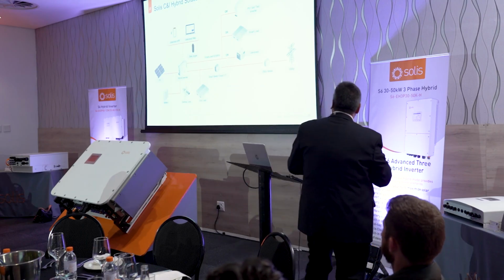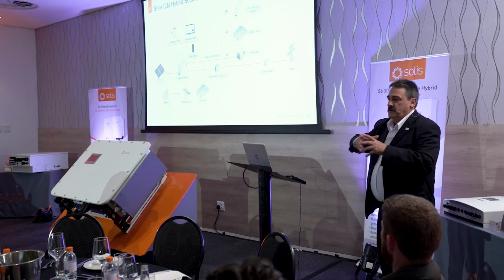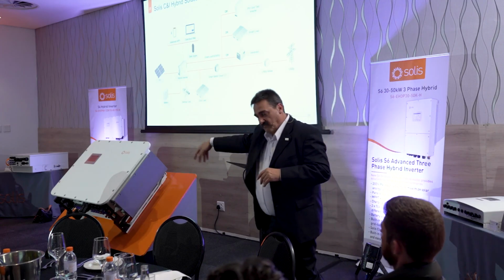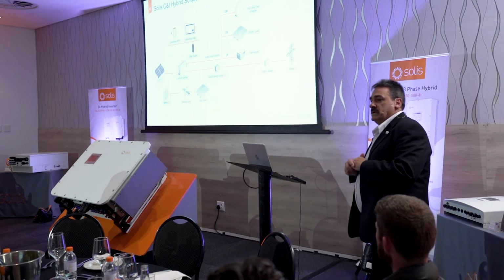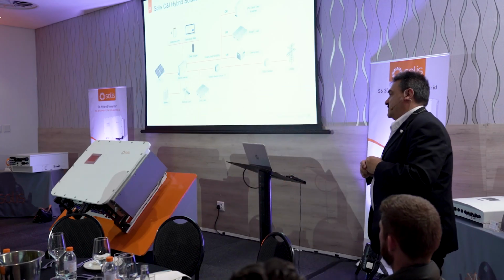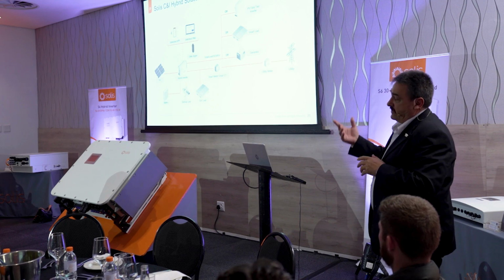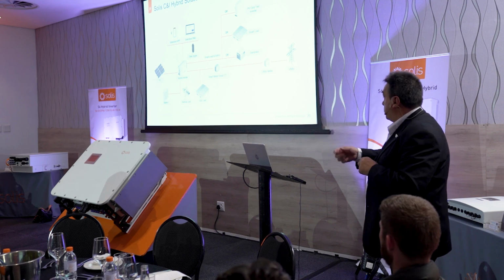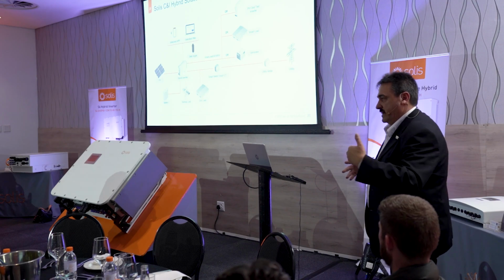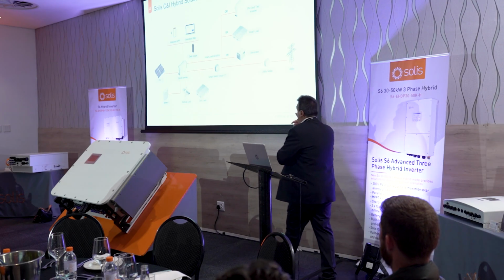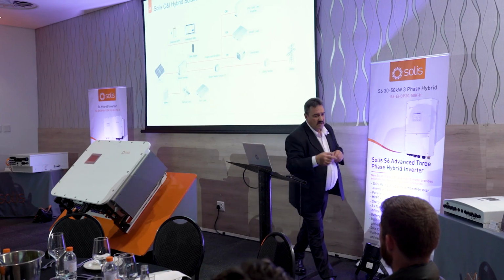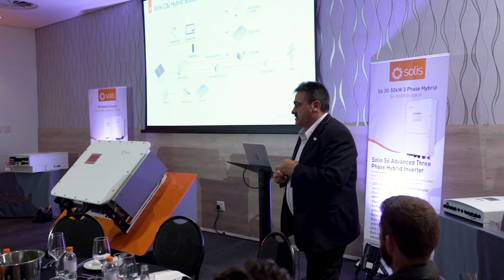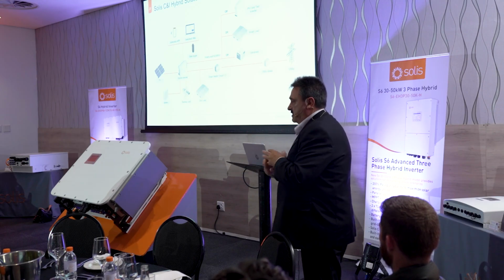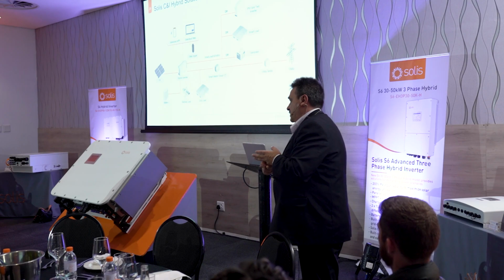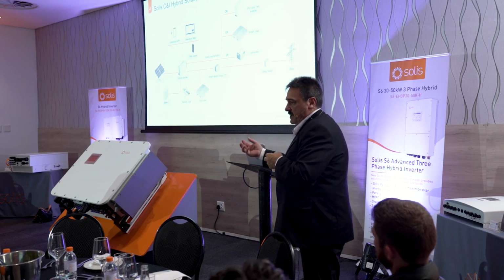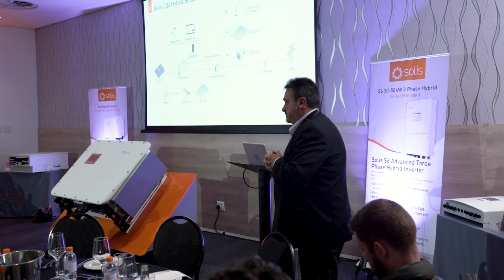When a generator is on site, a lot of installs have guys put 4 units in parallel for 500 kilowatts, but the generator on site might only be 300. So the installers worry that if the system starts drawing power, it'll kill the generator. We thought of that. The generator port, or smart port, can be set. So you can tell it you've got a 300 kVA generator on site, but when it draws power to help charge batteries or whatever, it can only take 200 or 250 kilowatts from it. It will always control the amount of power that comes into the system through that port.